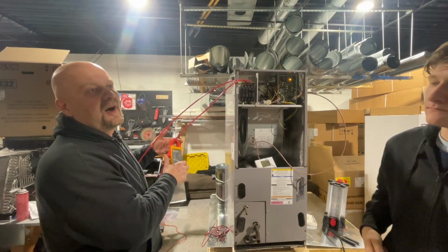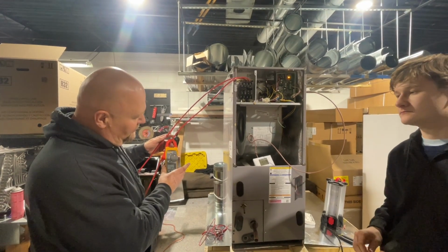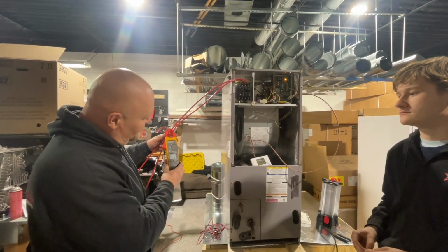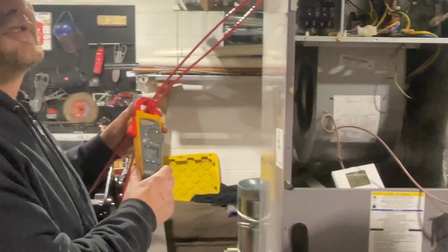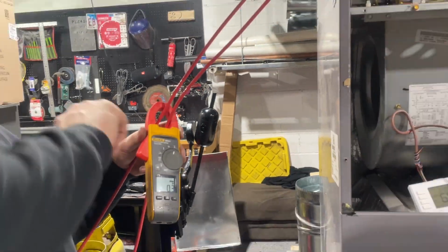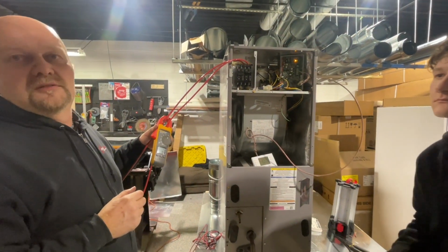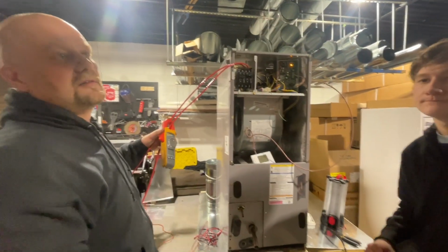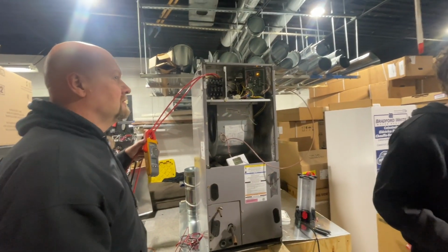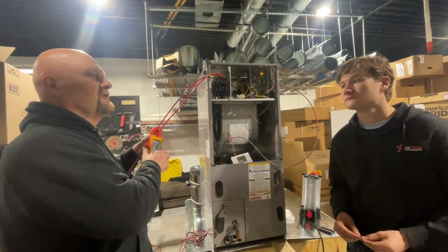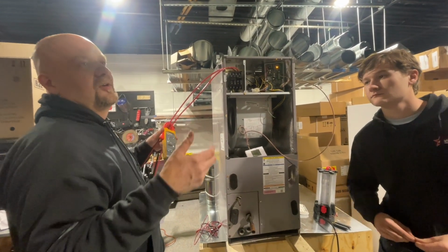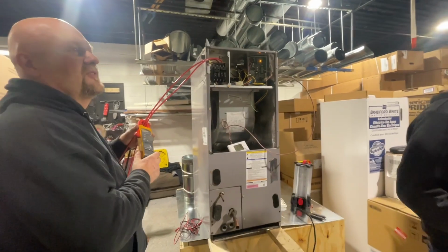Always check a single wire. See, I'm getting about 40 amps. If I put them together, I'm getting nothing. That's because we're reading opposite, because they're both working in different directions. That's why you're reading 0, plus and minus. Is it the same sequence of operation with the heat pump? No, completely different. But let's not muddy the waters today, because we can go over it another time.